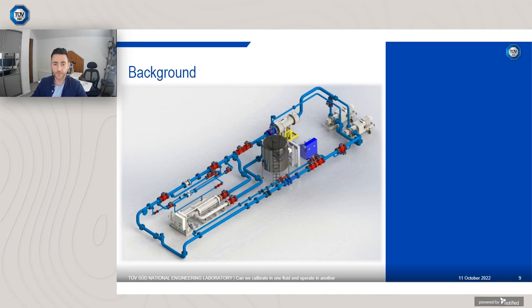So here's a schematic of it here just now. In terms of the facility, we use a small volume prover as a primary. It's a 60 litre small volume prover. We have 3 different helical turbine secondary reference meters. So they are calibrated against the prover and used as master meters ultimately.